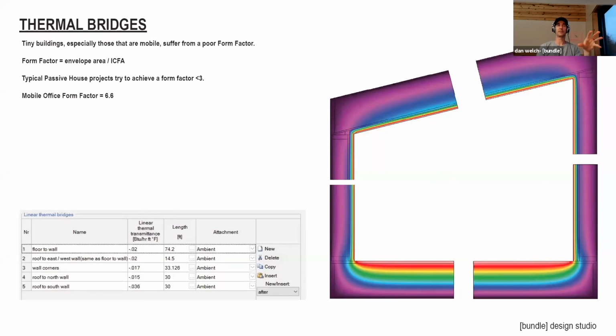The mobile office, because it has so much exterior wall area relative to such a small interior conditioned area, had a form factor over twice that. That makes it very difficult to control heat load, cooling load, and heating demand, since there are so many more surfaces experiencing heat loss. So one strategy we used was to count all of our negative thermal bridges.